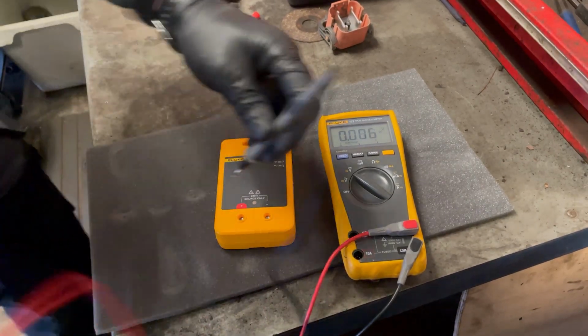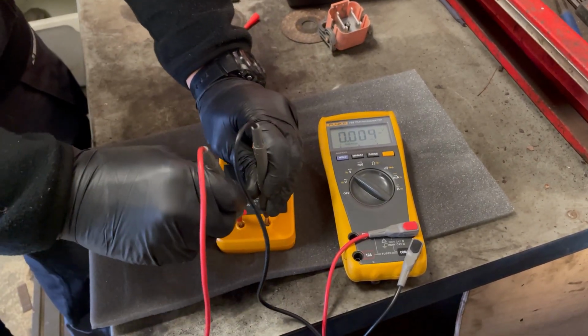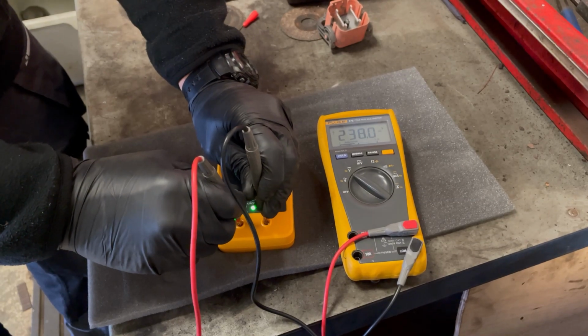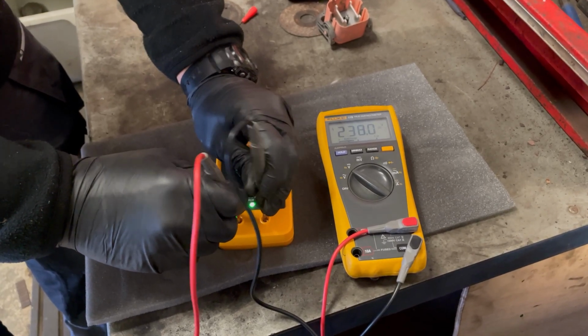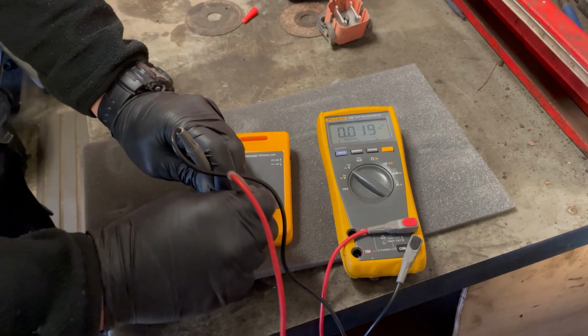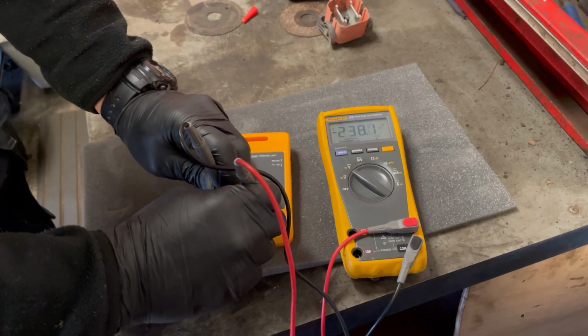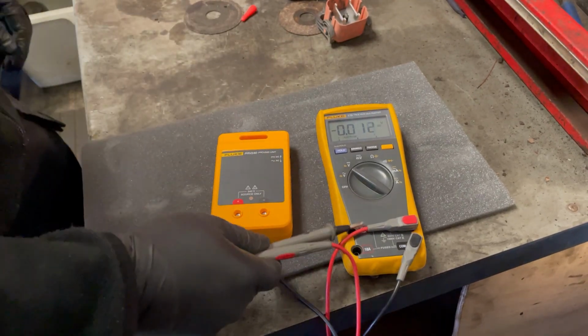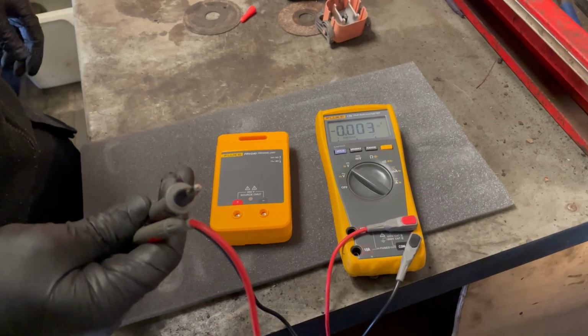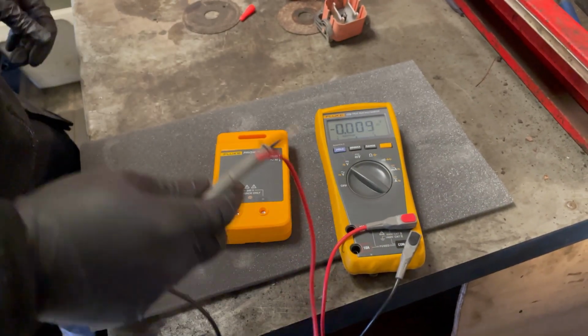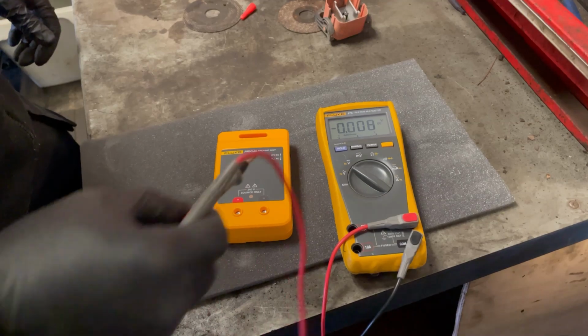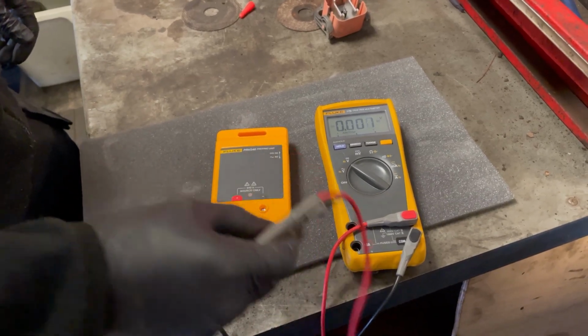So I'll put this across it just now. There it says 238 volts. I'll just swap the polarity around, and we've got minus 238. So the multimeter is working. We're going to double check that the high voltage battery, we'll need to put our PPE back on, is at 0 volts, and then we'll come back to the proving unit to make sure that this multimeter is still working.